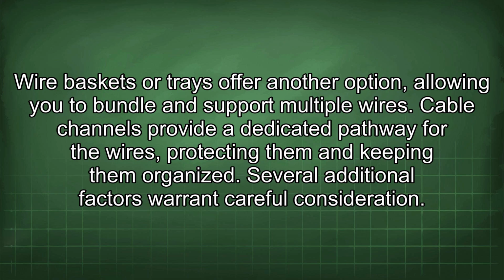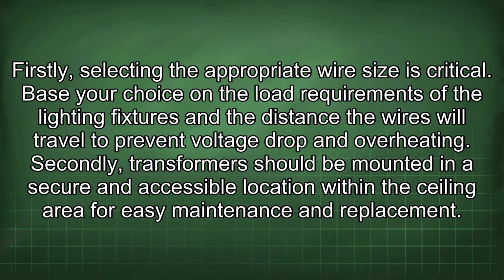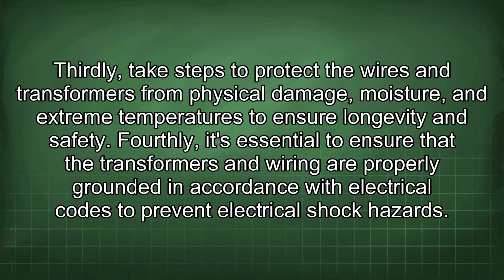Several additional factors warrant careful consideration. Firstly, selecting the appropriate wire size is critical. Base your choice on the load requirements of the lighting fixtures and the distance the wires will travel to prevent voltage drop and overheating. Secondly, transformers should be mounted in a secure and accessible location within the ceiling area for easy maintenance and replacement. Thirdly, take steps to protect the wires and transformers from physical damage, moisture, and extreme temperatures to ensure longevity and safety.